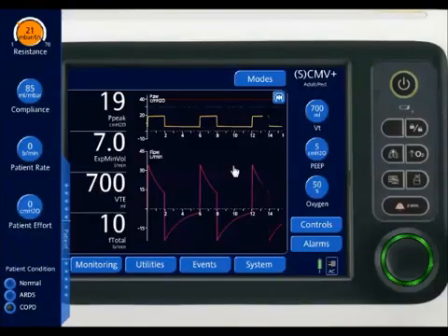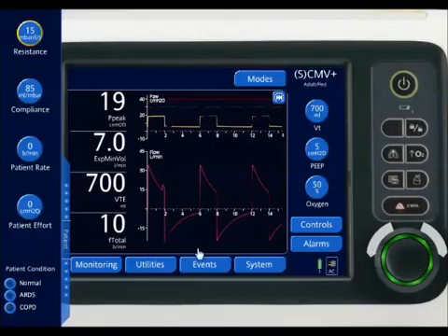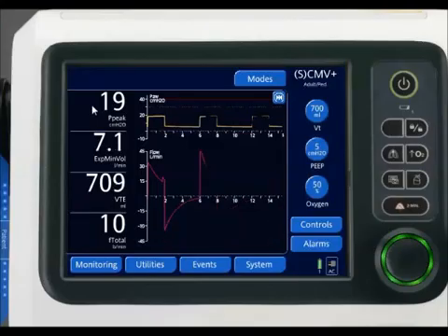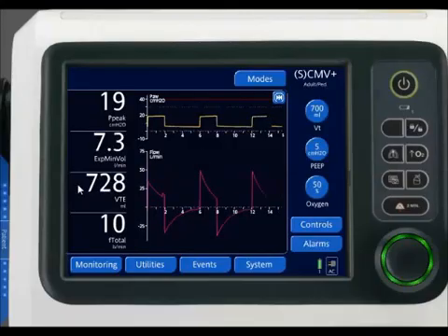Now I'm going to change my resistance to 15, and let's see what happens during adaptive pressure controlled ventilation. So I'm going to decrease my resistance. And since it is a pressure-based mode, I'm going to initially start getting higher tidal volumes. So we'll look over here on the left portion of the screen, our measured tidal volumes. There is some lag between breaths, because it's only going to adjust my breaths 2 centimeters of water between breaths. So my tidal volume is still going to go up until the ventilator catches up.